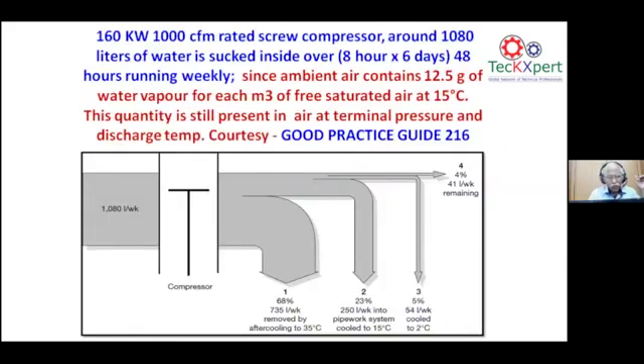So for a given compressor, 160 kilowatt, almost 1000 CFM it is giving as a delivery. Every week it is producing almost 1000 liters of water. 1000 liters of water is produced in a compressor, so whether it is removed correctly? Whether it is removed at the compressor house, almost 68% is removed at the post air cooler. So the post air cooler and the compressor hood should definitely work. If it is not efficiently working, definitely you need to have a post air cooler on the outlet of the compressor, because in many of the auto drain valves within the compressor hood, where we have gone for energy audits, everywhere it is just bypassed. So how will the post air cooler work when the water is not being pumped out through the auto drain?